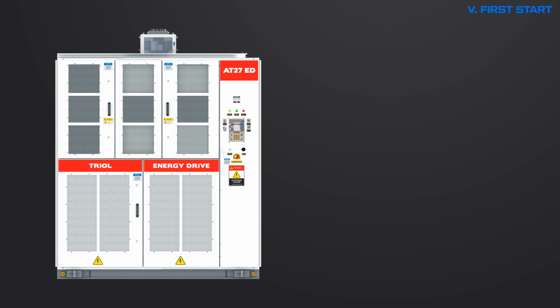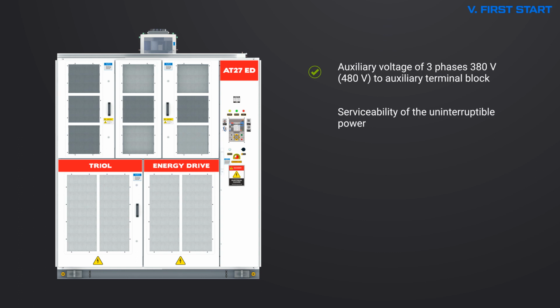First start. Our VFD is now ready for the first start. Let's turn on the AT27 for the first time, step by step. For this, we need to check the auxiliary voltage of 3 phases, 380 volt, 480 volt, supplied to the auxiliary terminal unit. Check the serviceability of the uninterruptible power supply, if any. Apply auxiliary voltage to the AT27 control system, making sure that circuit breakers do not operate when power is applied.